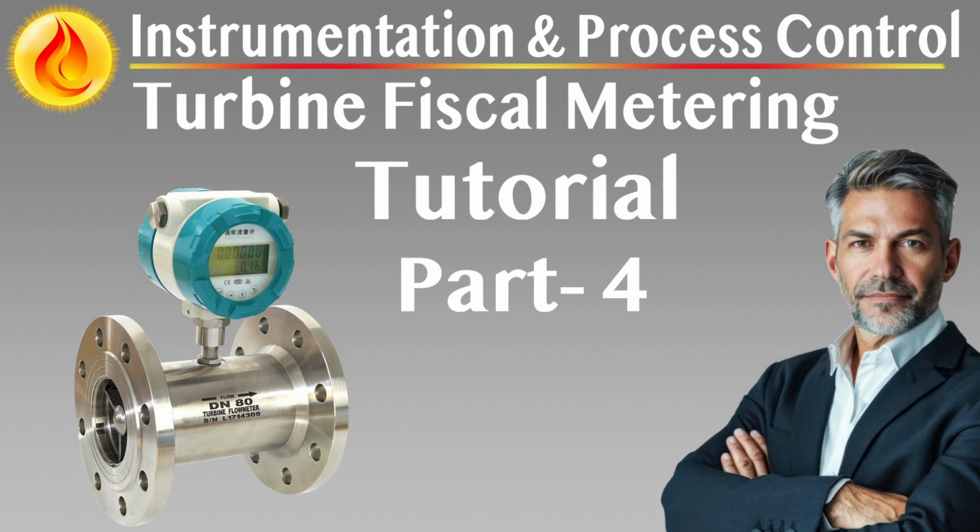These switches must be precisely aligned and tested during manufacturing to maintain the consistency of the calibrated volume, regardless of future detector replacements.